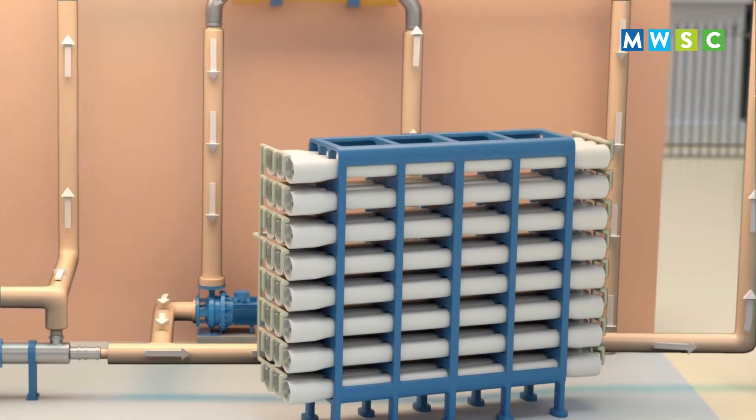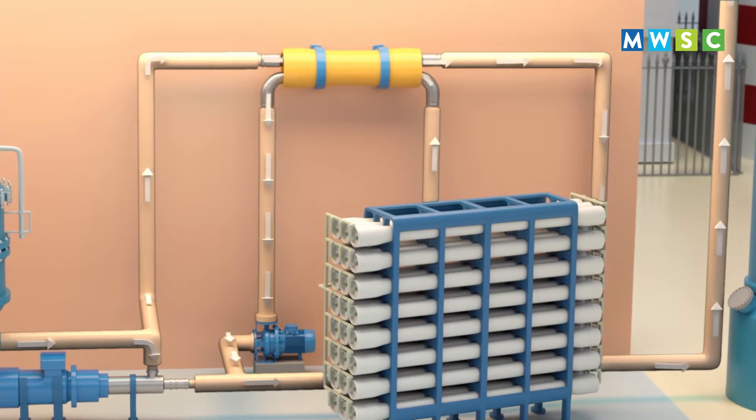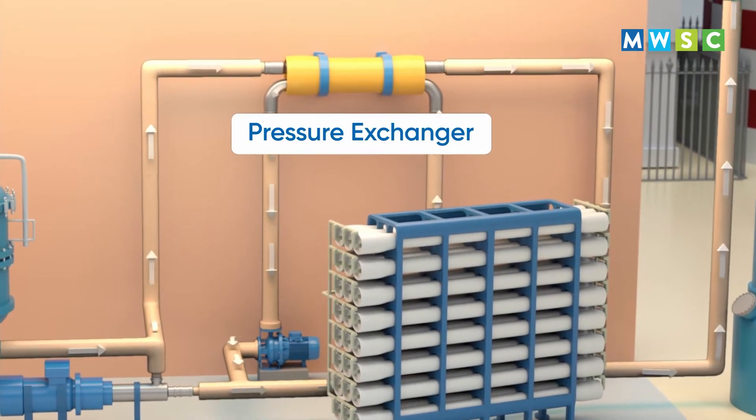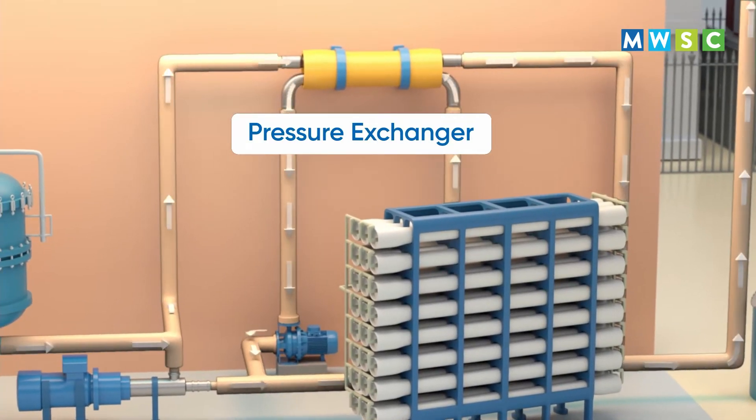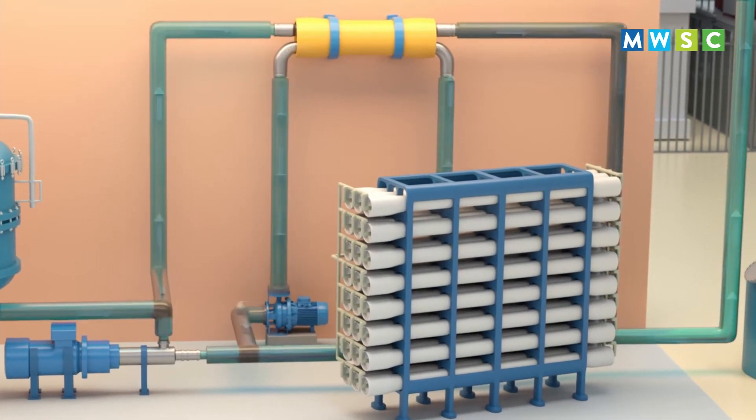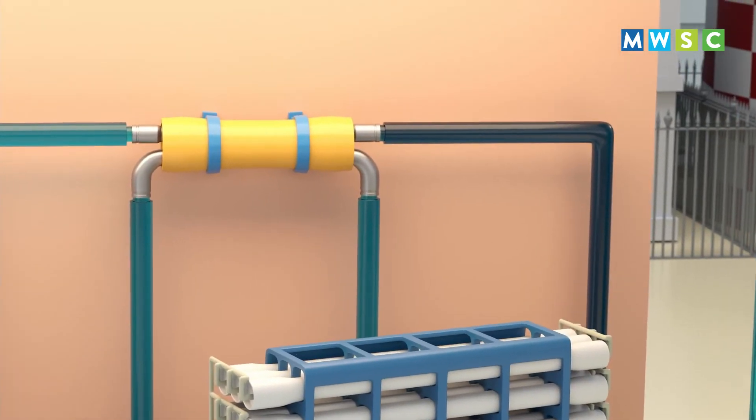This energy is recovered using a pressure exchanger, which helps to recycle up to 60 percent of wasted energy, driving substantial savings and reducing emissions. The rejected brine water is discharged into the sea.